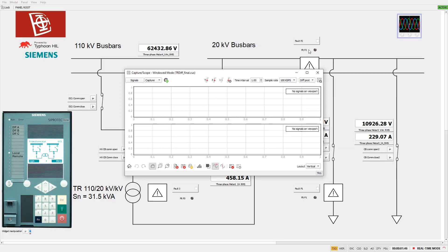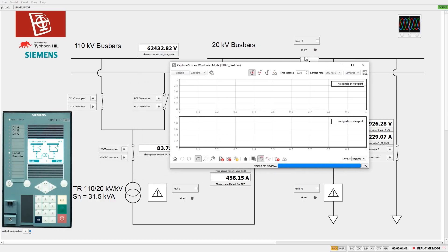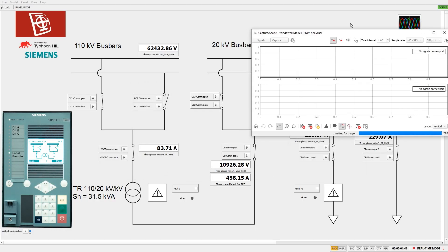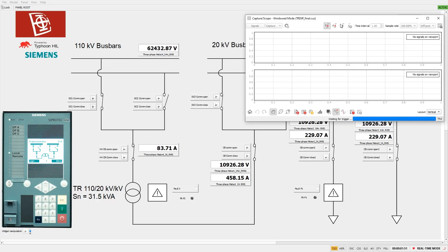In the case of a fault in the power transformer, the 7UT85 differential relay trips both the high voltage and the medium voltage circuit breaker after 100 milliseconds.